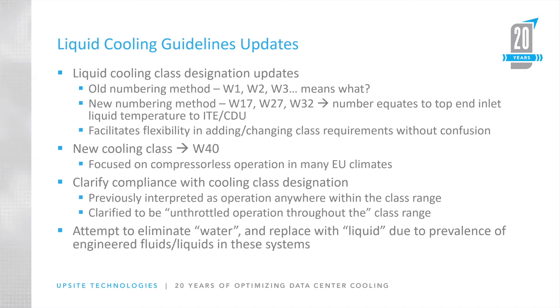The W40 class was added because a lot of climate scenarios in the EU can go compressor-less once you hit 40 degrees centigrade in the water. There are many solutions being designed around W40, but we were jumping straight from 32 degrees centigrade all the way up to 45 degrees centigrade — a massive temperature gap in the cooling classes — so we added W40 to fill it.